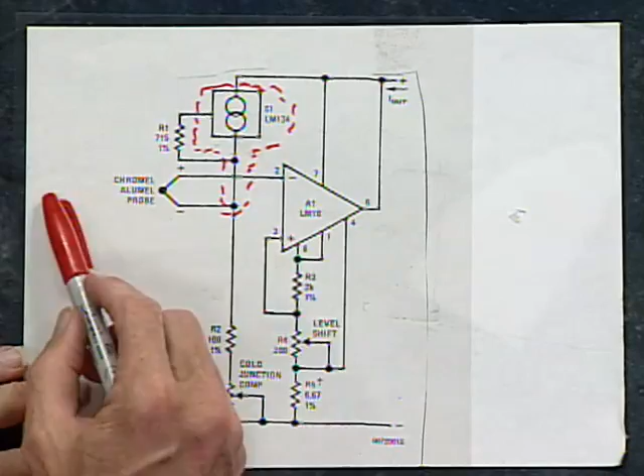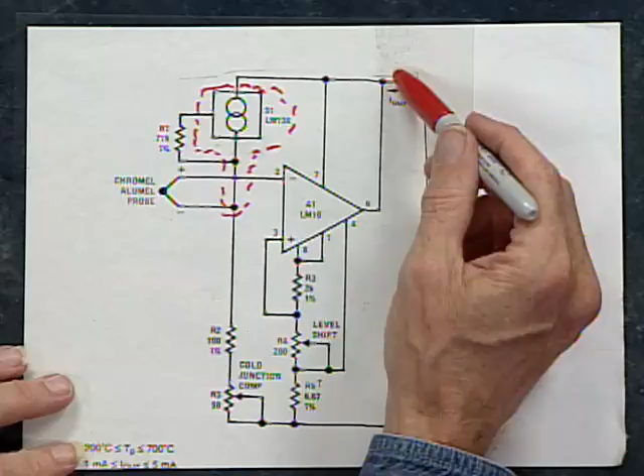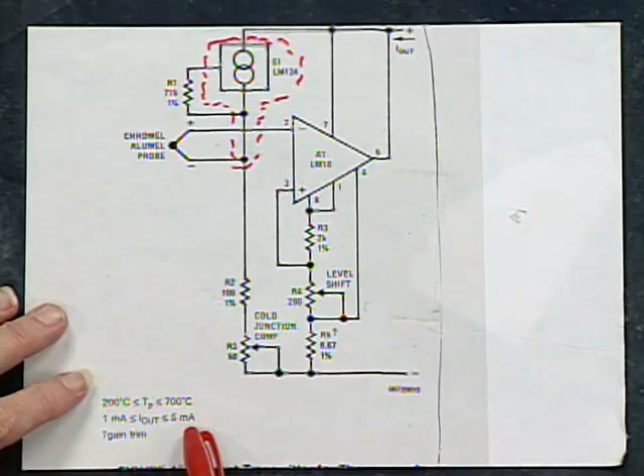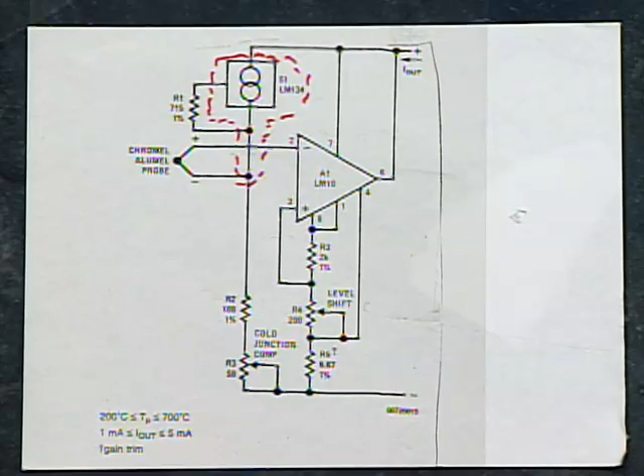This could be remote by 10 feet, 100 feet. So this is one way of using a current mode. It says 1 to 5 milliamperes, not 4 to 20, because some people don't want to waste a lot of current. The same principles that give you 4 to 20 milliamperes can be used for 1 to 5.